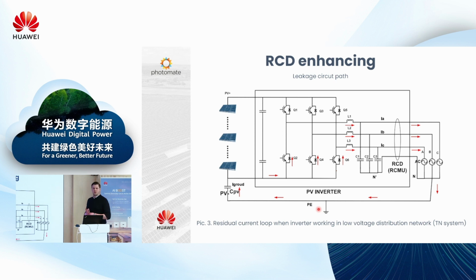In Sweden, the limit of leakage for the RCDs, the nominal current, is 30 milliamps, is that correct? So it's pointless when you have a system like 60 kilowatts, or 100 kilowatts - the 30 milliamps will be triggered all the time. So somebody who was thinking about this actually didn't consider this effect.